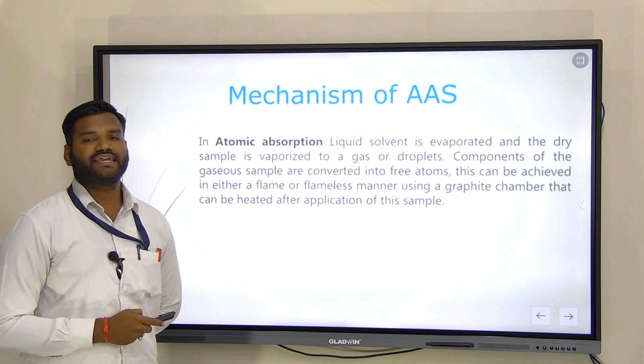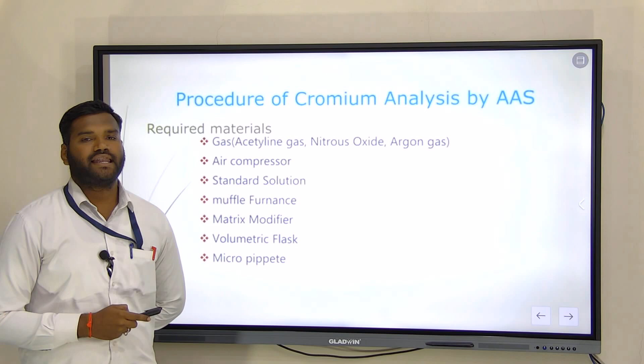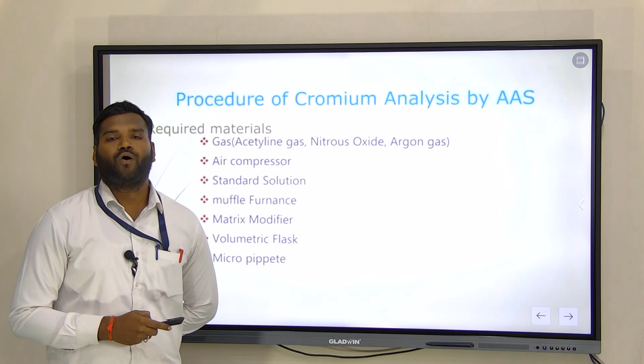Procedure for chromium analysis by atomic absorption spectroscopy. We can see the procedure for chromium analysis. In this we need required materials like gases: acetylene gas, nitrous oxide, argon gas, next an air compressor for the nebulizer, then standard solution, muffle furnace, matrix modifier, volumetric flask and micropipette.